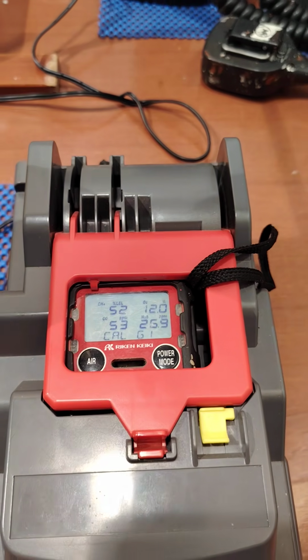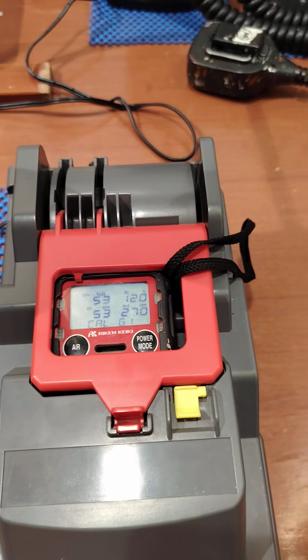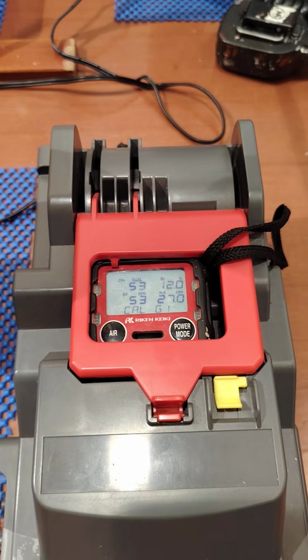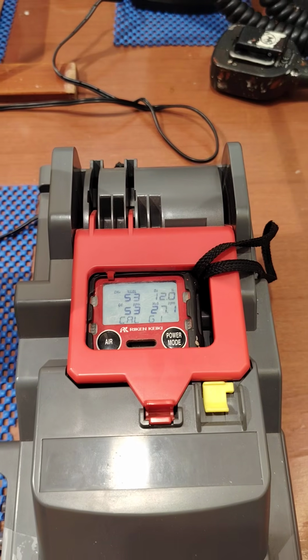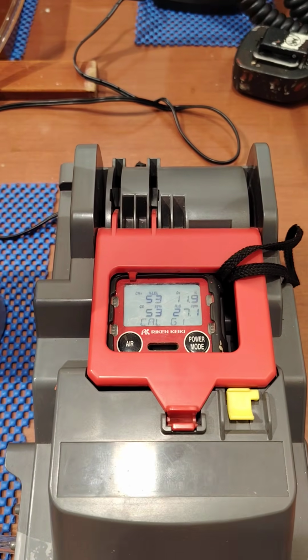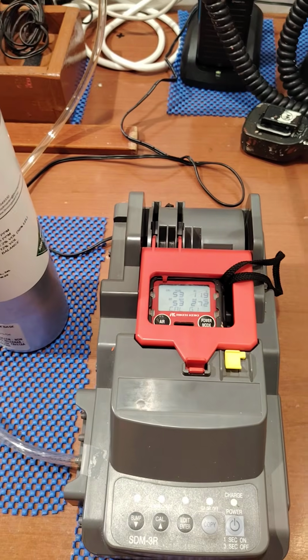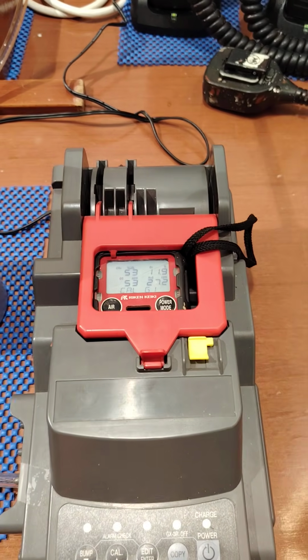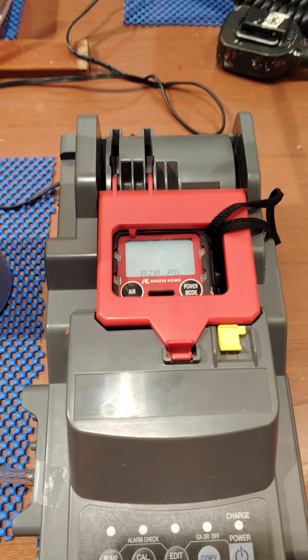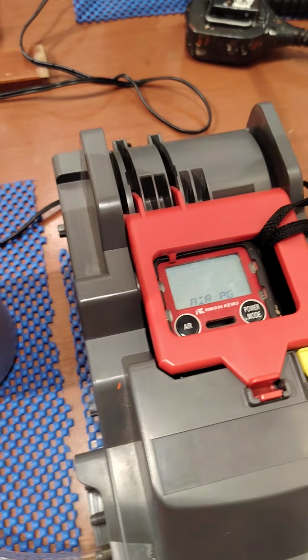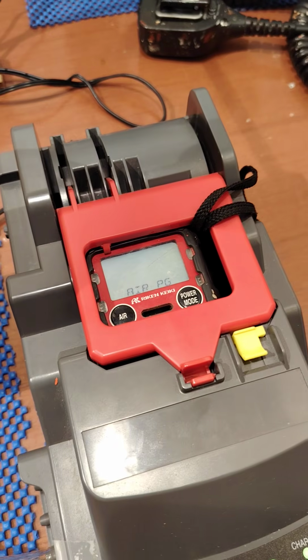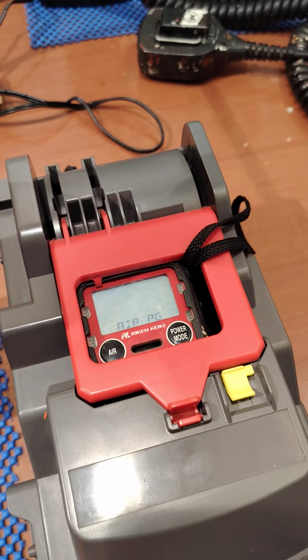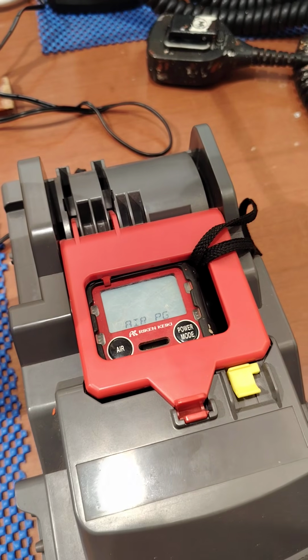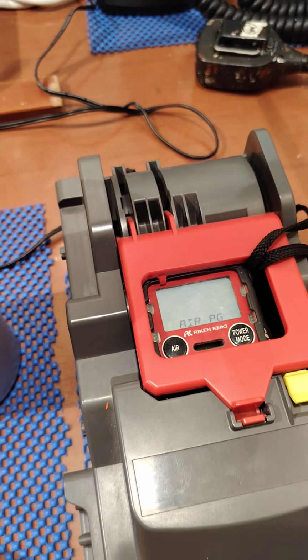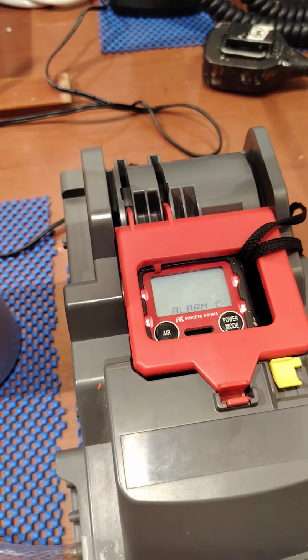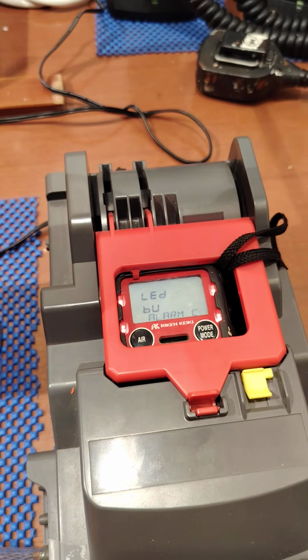so once it stabilizes actually, then it is going to automatically calibrate the personal multi-gas detector, so it is very easy. Okay, air purge, and then it is going to check the alarm, the LED, the lid, and then it will just only automatically stop. Then once it stops, it is completed.